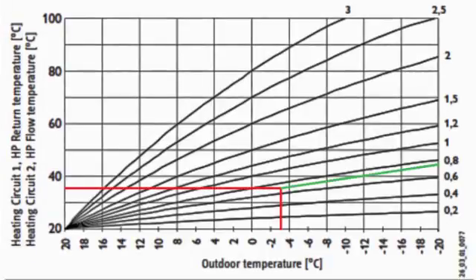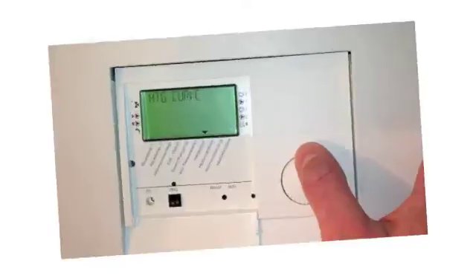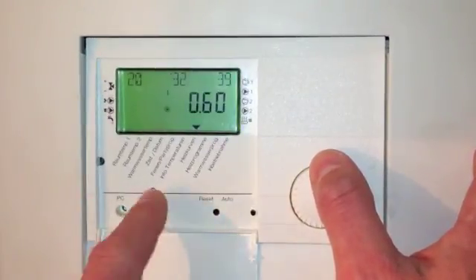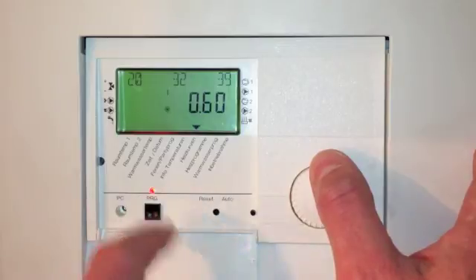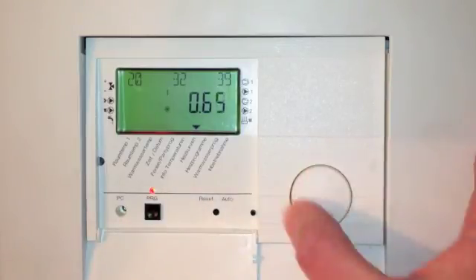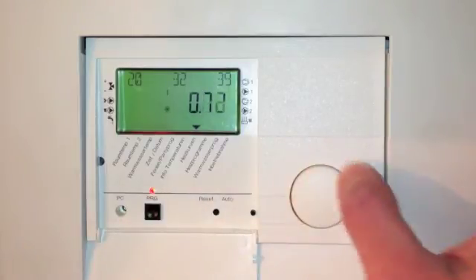To determine the right setting you need to know the design return temperature at the design outdoor temperature. For example, 35 degrees at minus 3 outside gives a curve of approximately 0.78. To adjust the heat curve, enter the heat curve menu. It's factory set to 0.6. Use the program button to access the setting adjustments and use the jog dial to change them.